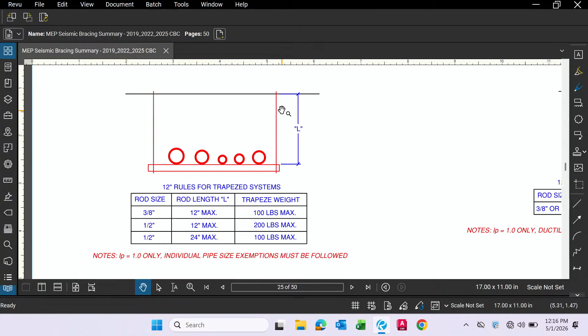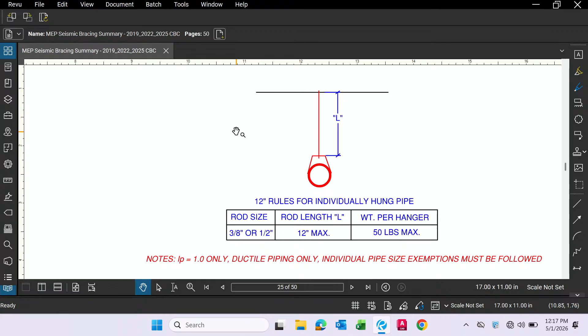So as you can see, it becomes very hard to apply on any project, because by the time you apply this 12-inch rule, you pretty much just apply it to the pipes that don't need to be braced to begin with. For the 12-inch rule for individually hung pipe, it only applies to piping with 3/8 or 1/2 inch rod, and the weight of the pipe at that location is no more than 50 pounds. So the intent of the 12-inch rule in the code is just to make sure that it only applies to very small pipes or components that don't weigh a whole lot. For ductwork it is pretty much the same. It only applies if the ductwork has an importance factor of 1.0. 3/8 inch rod, 100 pounds; 1/2 inch rod, it goes up to 200 pounds, and so forth.